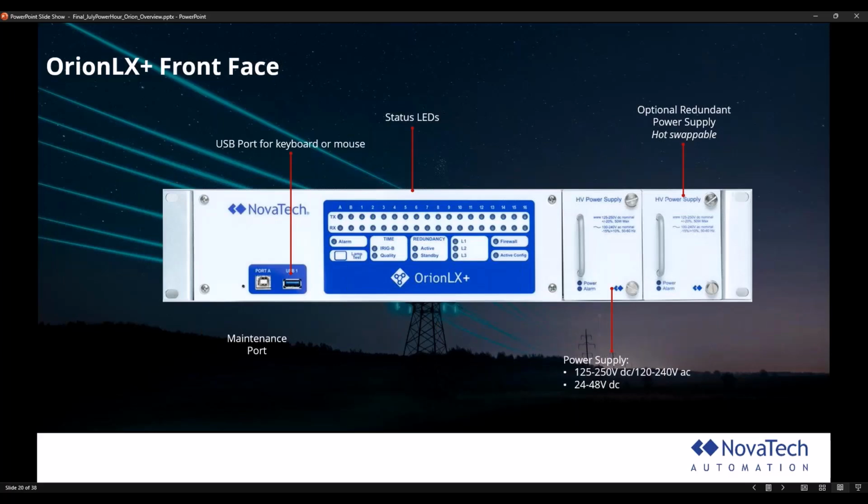Okay, from the front here, you have redundant power supplies. These are SCADA enabled, so you can actually pull points off of them, monitor voltage, monitor health, do things like that. You can hot swap them too. So this is really your long range, best future-proof-est solution. Making up words today, but you have options here for low or high voltage. Note the cutoff change is at 48 on this one, which is a little bit different than in the past. That's just by nature of the modular supply being different than the old CPX. So the 48 volt cutoff, I would point out to you. Make sure you also can spec one of these as high voltage and one of these as low voltage. So you actually have the widest range possible on these. These are higher performance. They can support more power, and of course they're SCADA enabled and fancy things like that, as is fitting to a flagship product.